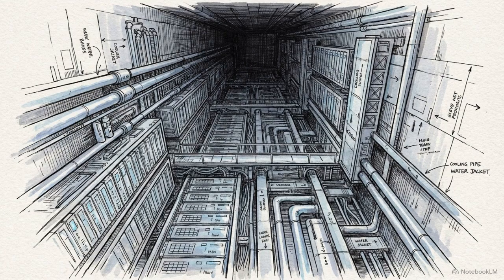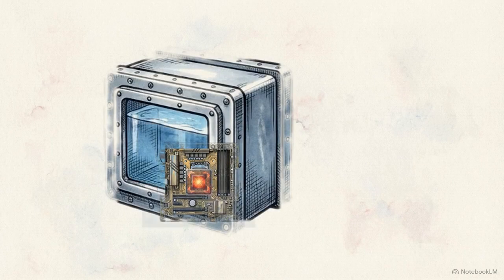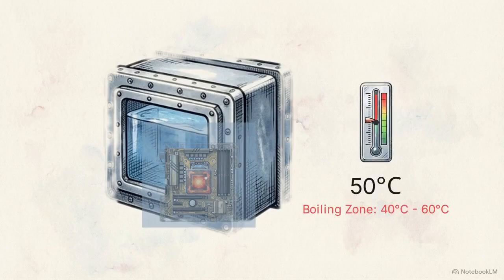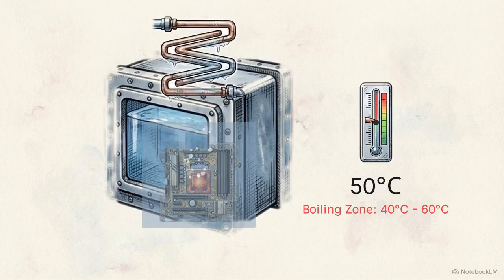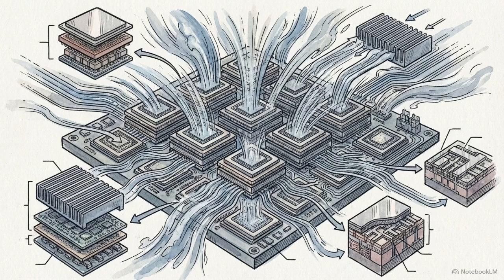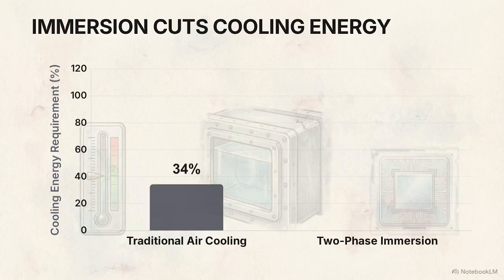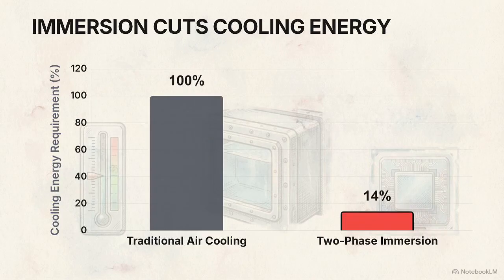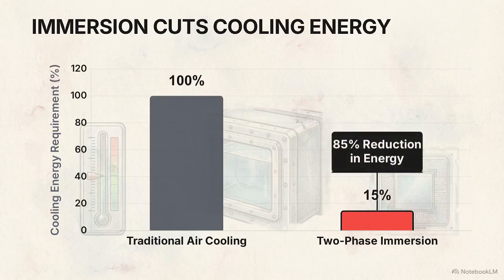For organizations chasing the absolute ceiling of current thermal management, there is a final tier: two-phase immersion cooling. Two-phase systems submerge servers in a specialized fluid engineered with an intentionally low boiling point, typically sitting right between 40 and 60 degrees Celsius. As immense heat radiates off the chips, the surrounding fluid actively boils into vapor, absorbing massive thermal energy. That vapor rises to condenser coils, cools back to liquid, and rains back down into the bath, creating a continuous, pump-free loop. Leveraging the physics of phase change unlocks extreme densities of 100 kilowatts or more per rack. And because it eliminates the need for mechanical pumps or fans, it cuts overall cooling energy consumption by 80 to 90%. The trade-off is strict.